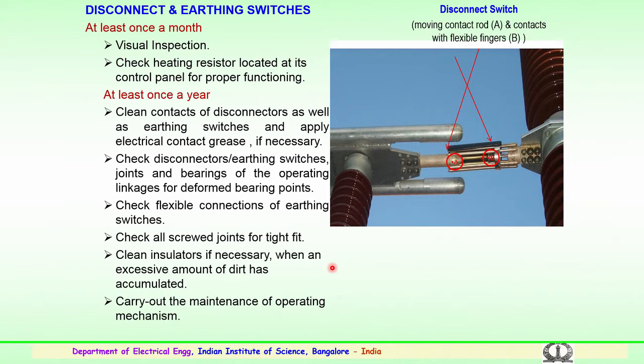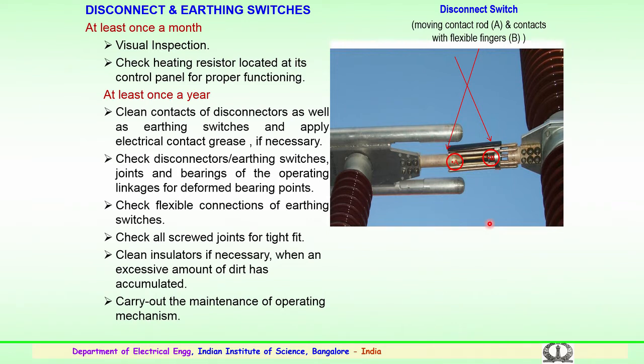Then comes the disconnector or the earthing switch. The disconnector switch comprises a moving contact with flexible fingers. These disconnector switches vary with different voltage levels, and various types are employed at different voltage levels. These disconnecting switches have to be attended at least once a month — a proper visible inspection must be made. A necessary check has to be maintained for heating, particularly near the contacts, at its control panel, whether there is proper functioning or whether the contacts have been corroded and need inspection and remedial action.